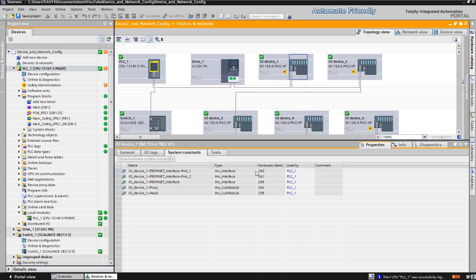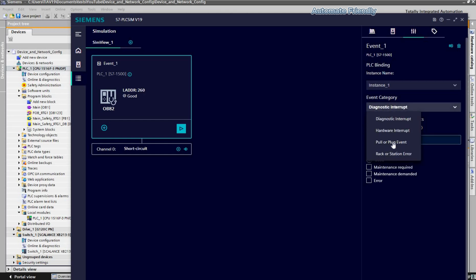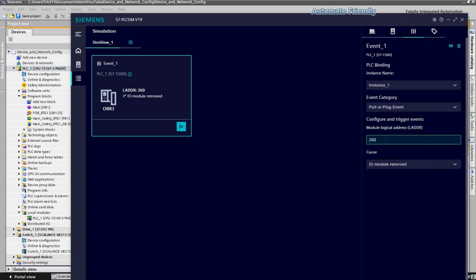Here we can see the identifiers of IO device 1, and the Profinet identifier is 260. I will insert this parameter value 260 into the module logical address field, and then select the pull and plug event in the event category section. Then in the cause section, I will select IO module removed, and then click on the play button.